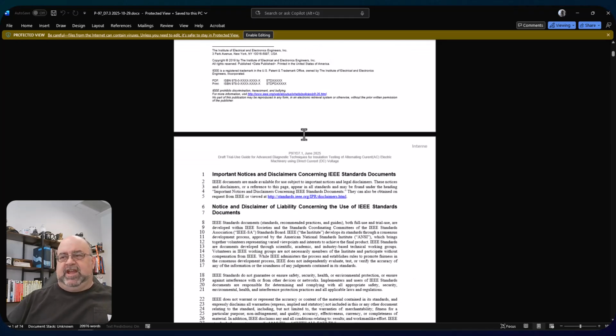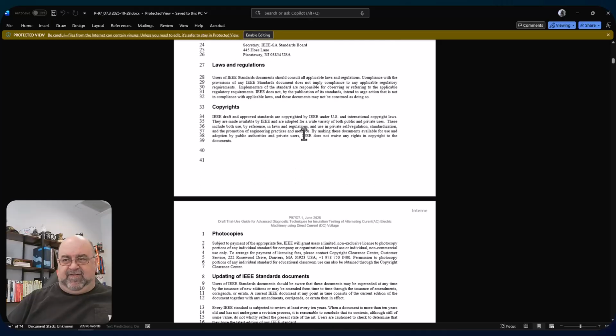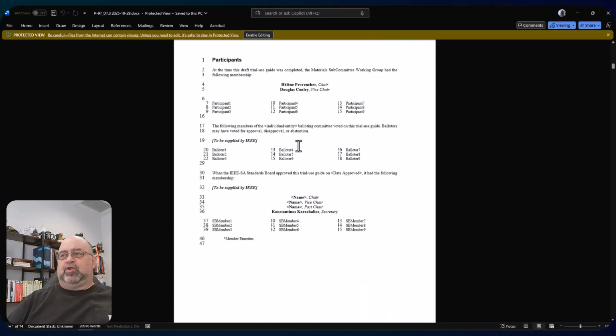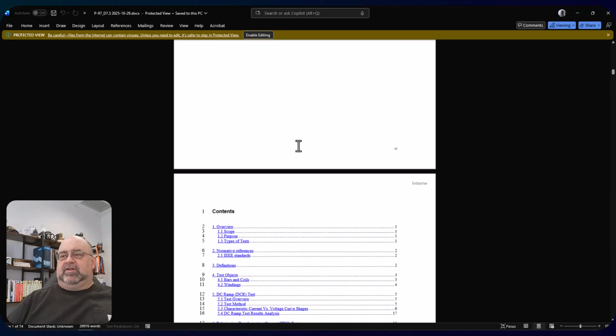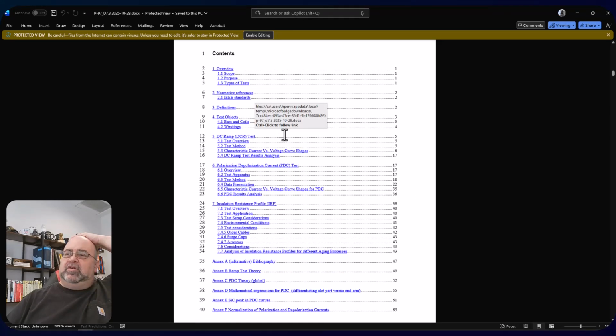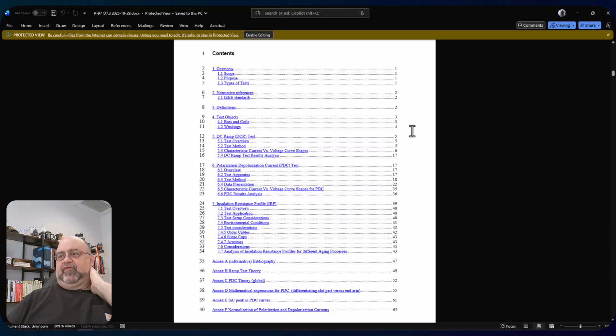Well, this is the standard where we finally include insulation resistance profile. We also include some other stuff, like how to perform your DC ramp test, and also your polarization-depolarization test, which, to be perfectly honest, prior to this I hadn't heard of. It's something done at Hydro-Quebec and some other places. It was introduced, I remember, in the early 2000s. It was discussed in the group to include in the 2013 version of IEEE Standard 43, which we'll cover next.